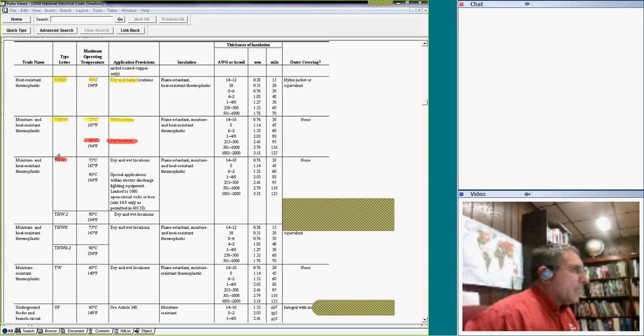Right? Look at this one, guys. The same thing. THW, 75 degrees, damp or wet location, 90 degrees only with special permission. This guy, 90 degrees, dry or wet location. Bring it on. Look at this one, THWN-2, 90 degrees, dry or wet. If it has a 2, it's 90. If it's W, it's only 60. Don't even think about it. UF, it's only 60. Don't even think about it.